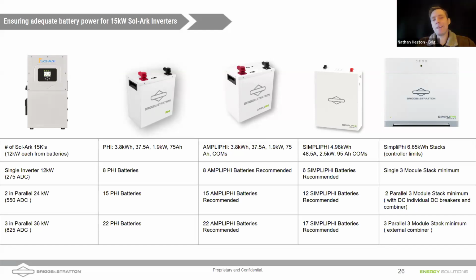Yeah, absolutely. You can limit how much power the Sol-Ark will pull from a battery bank by manually setting the power output of your inverter. But if you're buying an inverter with a certain power output, you want to meet that. To get that power demand, our AmpliPhi and PHI batteries run at a C/2 rate, meaning they can output half their total capacity in an hour. The 4.9 battery is also C/2, while the 6.6 is a 1C rating. The communicating batteries will automatically request the Sol-Ark to limit output power, so there's a minimum number of batteries needed to attain the full capabilities of the inverter.